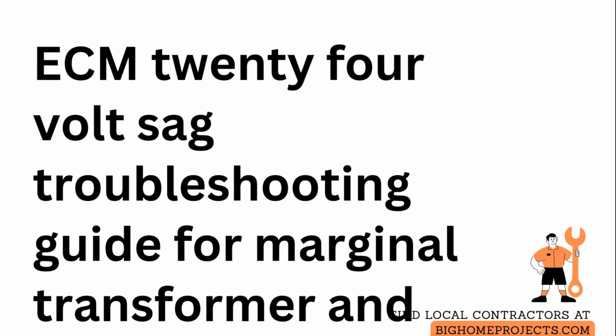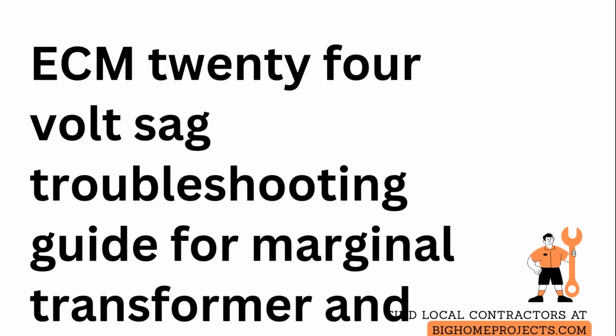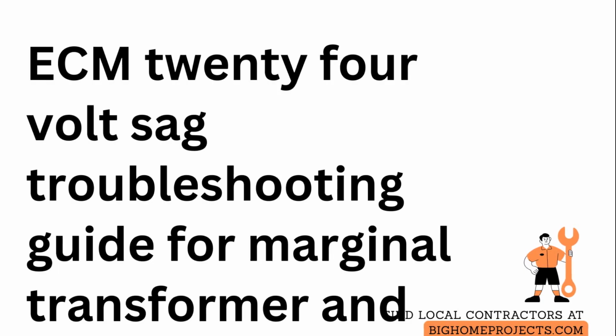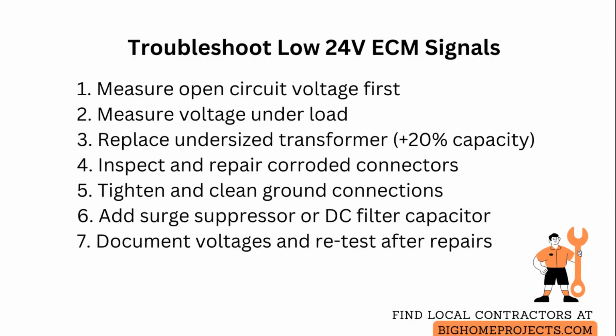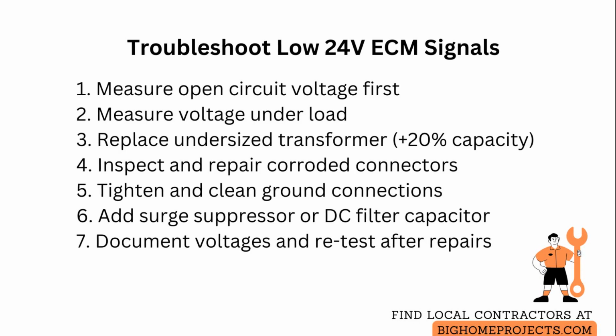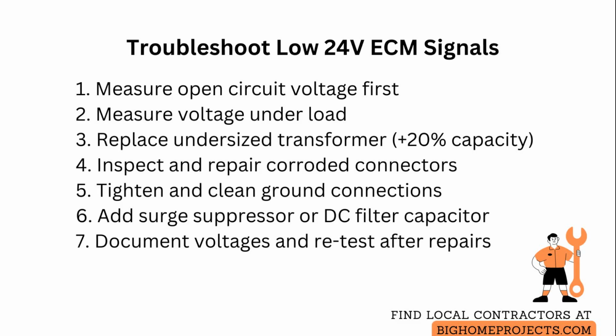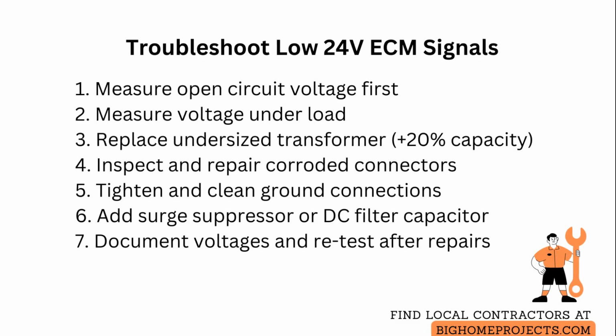Partial or low 24-volt signals to the electronic control module can cause erratic operation or a failure to start. A marginal 24-volt supply usually shows up as intermittent faults, slow actuator response, or control logic resets.